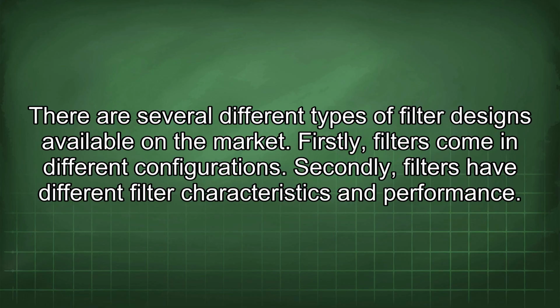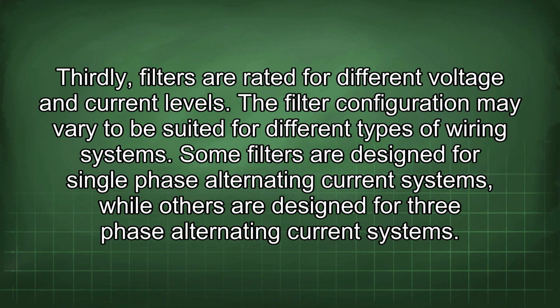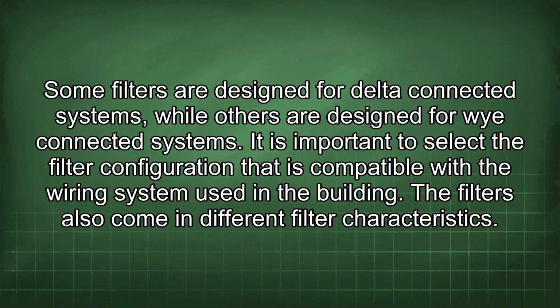Firstly, filters come in different configurations. Secondly, filters have different filter characteristics and performance. Thirdly, filters are rated for different voltage and current levels. The filter configuration may vary to be suited for different types of wiring systems. Some filters are designed for single-phase alternating current systems, while others are designed for three-phase alternating current systems. Some filters are designed for delta-connected systems, while others are designed for Y-connected systems. It is important to select the filter configuration that is compatible with the wiring system used in the building.